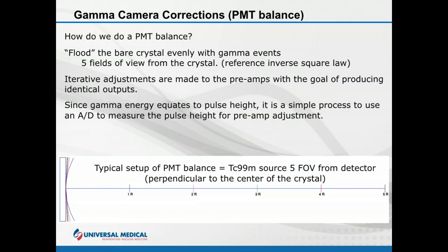On some older systems, PMT balance might require total manual adjustment — physically adjusting every photomultiplier tube. On modern cameras it is done via computer control. The process floods the bare crystal and the computer measures pulse height via an A-to-D converter, making iterative adjustments to the preamp until all outputs are equalized.